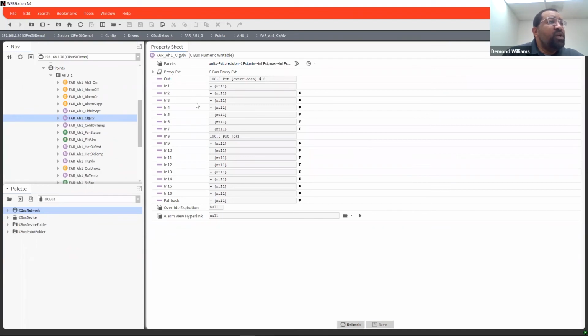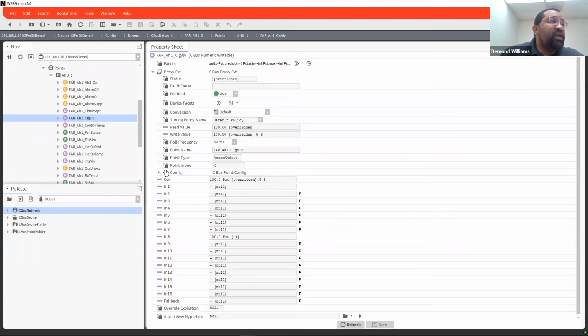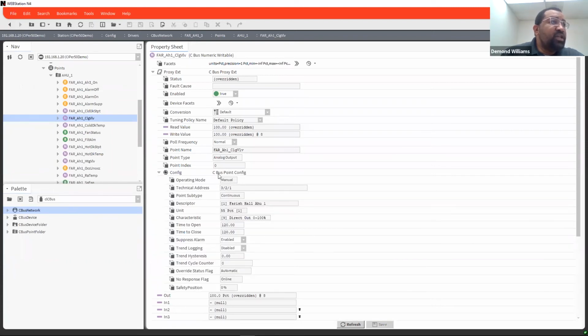If you go into the AX property sheet, one of the cool things is if you get into a point where you want to actually do a controller change out and none of the wires are labeled and you kind of want to find out what parts are on what terminals, if you go into the AX property sheet and right here under your proxy extension and then right here up under config, this is where it says technical address, basically tells you where that part is. So this is basically controller 3, module 2, input number 1. That way you know exactly where those parts are.